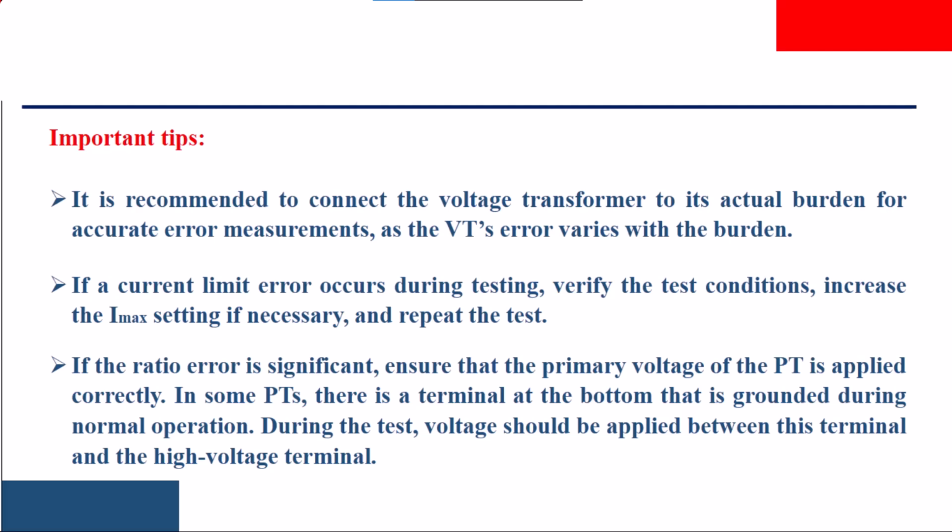If the ratio error is significant, ensure that the primary voltage of the PT is applied correctly. In some PTs, there is a terminal at the bottom that is grounded during normal operation. During the test, voltage should be applied between this terminal and the high voltage terminal.